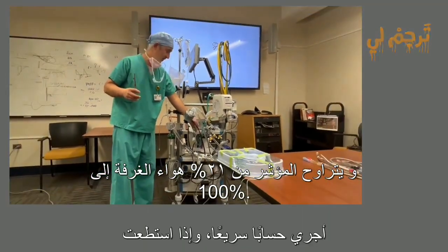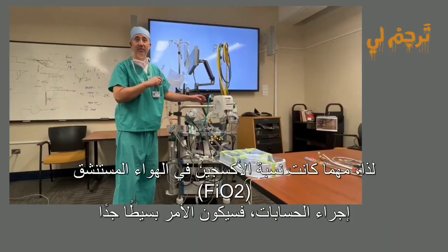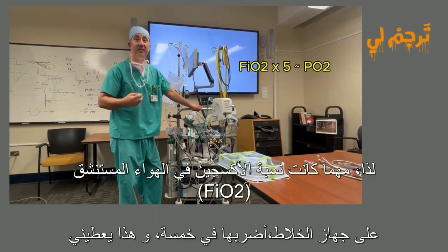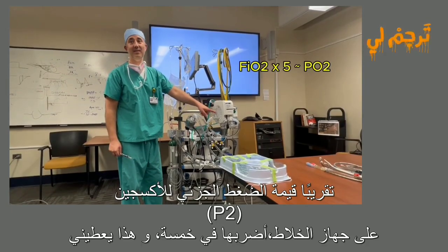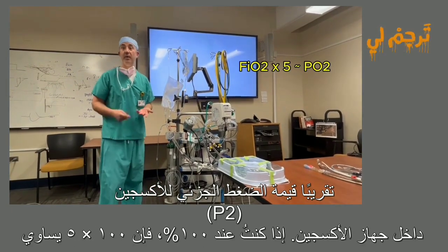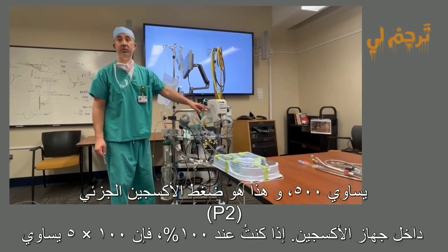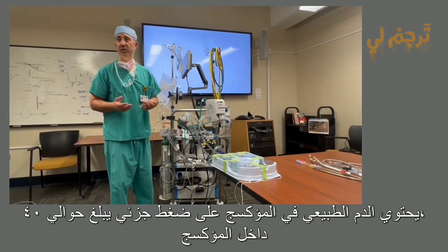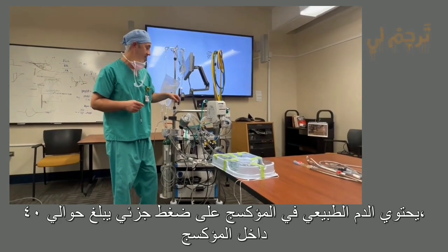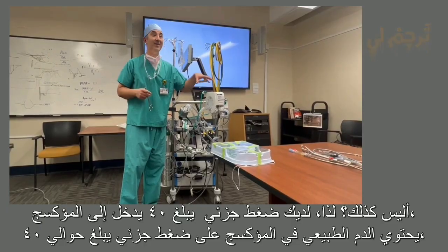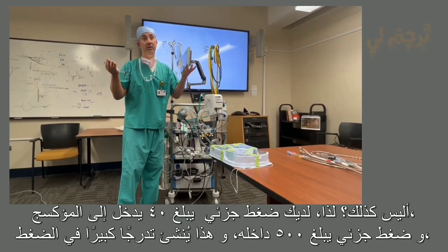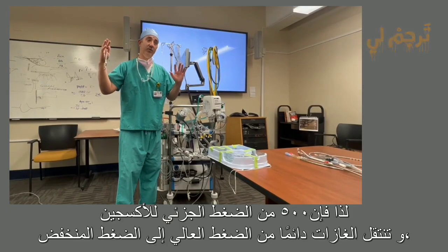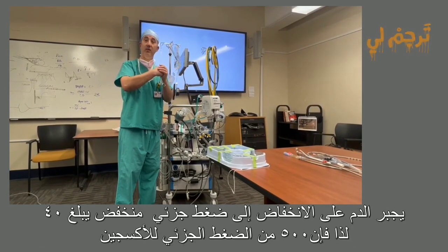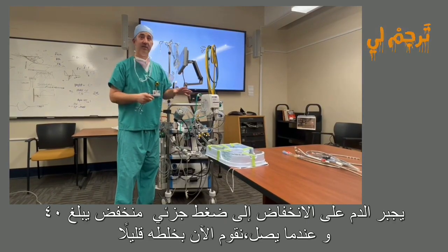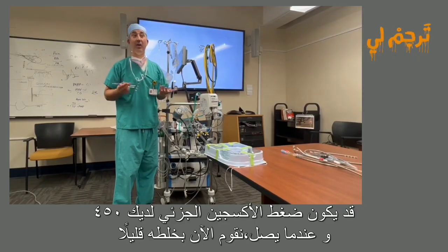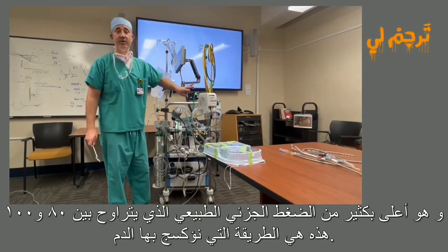I do a quick calculation, and if I can do the calculations, it's pretty simple. So whatever my FiO2 is on my blender, I multiply it by 5, and that gives me roughly what the PO2 is inside the oxygenator. So if I'm at 100%, 100 times 5 is 500. That will be what the PO2 is inside the oxygenator. Venous blood, if it's normal, has a PO2 of about 40, right? So you have PO2 of 40 going in, 500 inside of it. So it creates a huge pressure gradient. And gases always go from high to low. So that 500 of partial pressure of oxygen forces it into that low 40 PO2. So when it comes out and mixes a little bit, your PO2 might be 450, but much higher than a normal PO2, which is like 80 to 100. So that's how we oxygenate the blood.